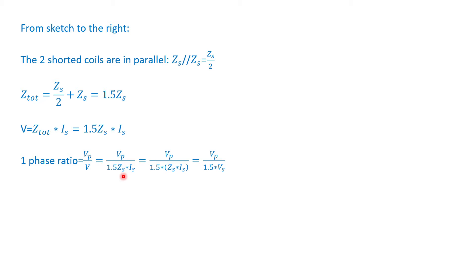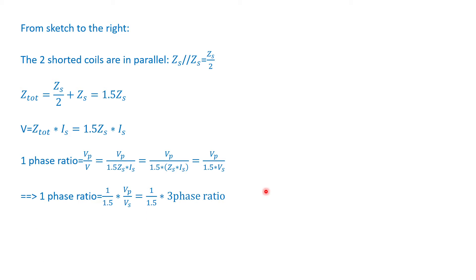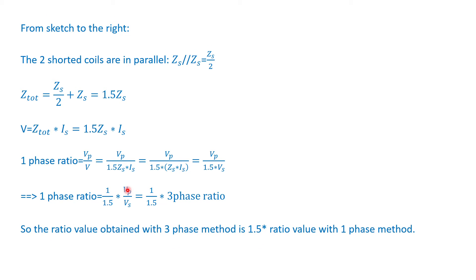The primary voltage we can measure directly. The measured secondary voltage in this case is 1.5 times the secondary impedance times the secondary current. Rearranging, the secondary impedance times the secondary current is just the secondary phase voltage, so we get the primary voltage divided by 1.5 times the secondary voltage. Therefore, the single-phase voltage ratio equals (1/1.5) times the three-phase voltage ratio — meaning the three-phase ratio value is 1.5 times the single-phase ratio value.